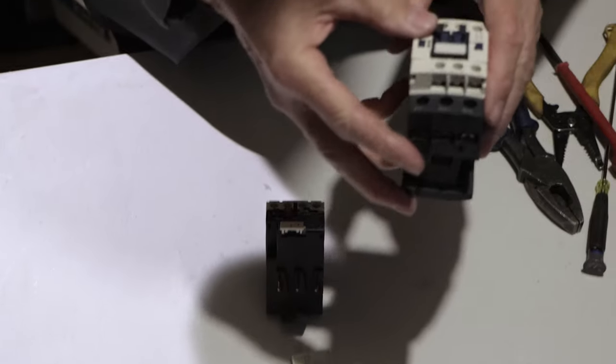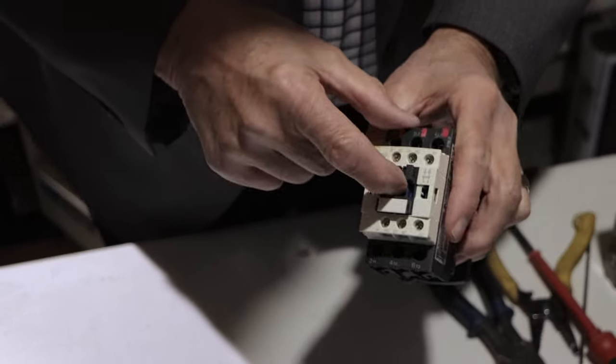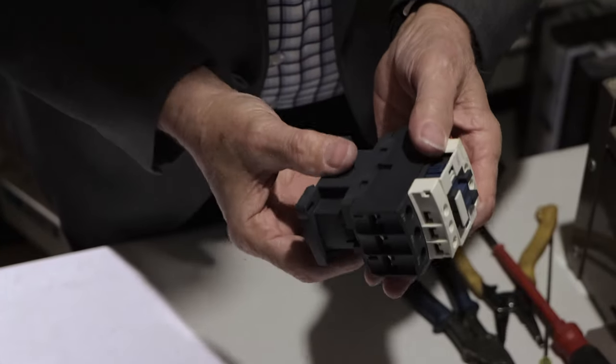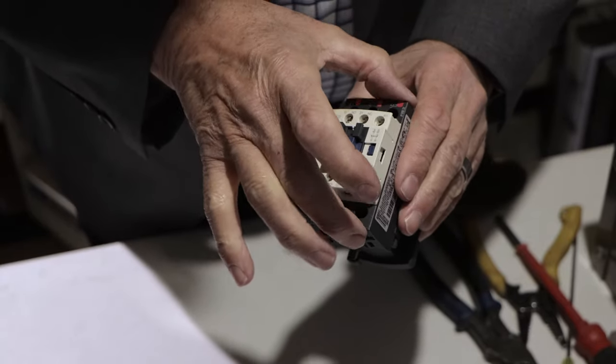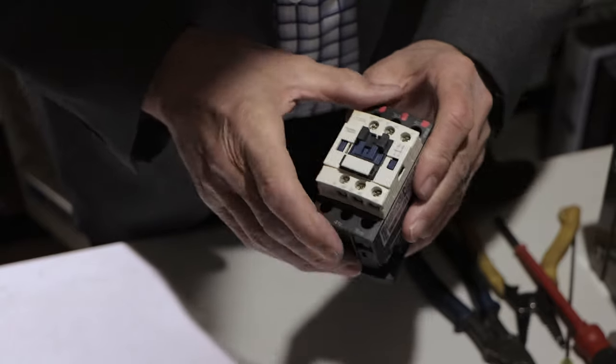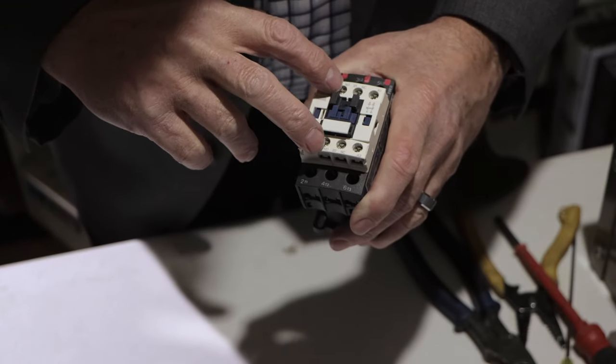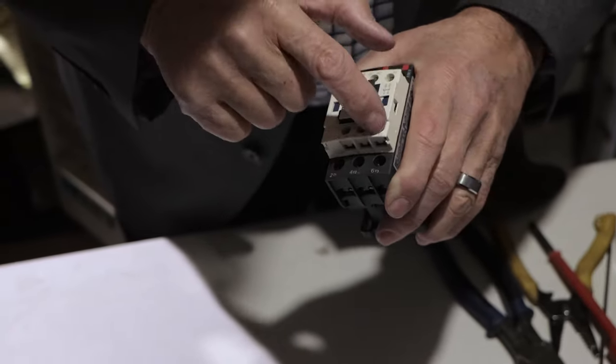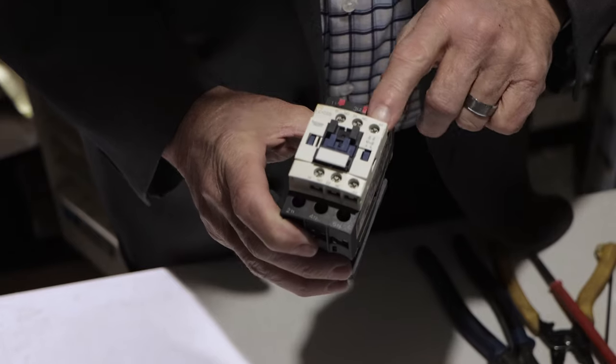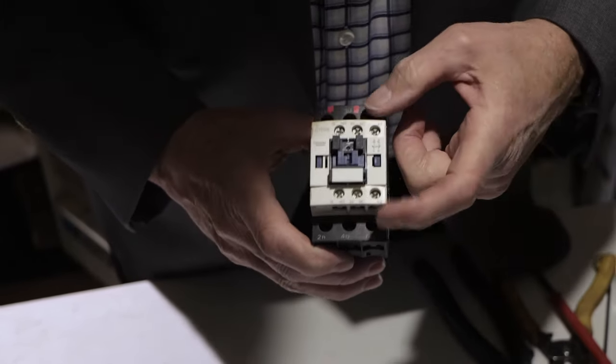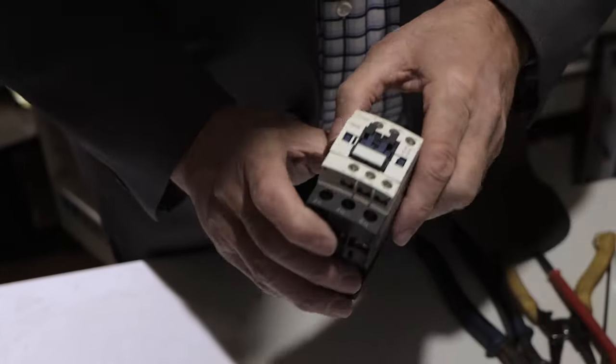We've got basically what we would call the starter, which is the contactor part, and we've already reviewed how we use the electromagnetic field in the magnet to draw the plunger down, and make contact between A phase, B phase, and C phase, and at the same time, we can close the normally open set of contacts, and open the normally closed set of contacts. And these right here, these are our coil windings. So A1 would be wire, typically wire number three, and A2 would be the neutral. So this is where the conductors are going to make contact with the winding, the coil.